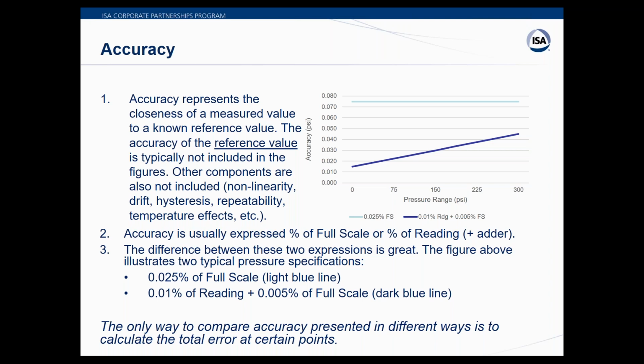When we talk about accuracy as a number, most often we see percent of full scale. Maybe for flow, it could be a percent of reading plus a fixed component, some type of adder. I call that a compound statement when it has percent of reading and percent of full scale. Depending on what somebody says on their specification, it can make a lot of difference. So we tried to show you a graphical representation here. Here's an instrument. If you say it's 0.025% of full scale, and that's a pretty tight number, we've graphed that in blue, but notice that we're saying the span is 300 psi. So if you take the 0.025%, that's going to calculate to 0.075, and the accuracy would meet that specification over the entire range.